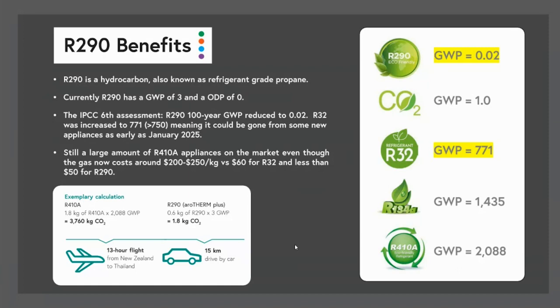So if we took an R410A appliance with 1.8 kilos of R410A, then you multiply that by its global warming factor, you get 3,760 kilos of CO2 as the environmental impact in terms of carbon footprint from that appliance if all of that refrigerant was released into the atmosphere. And that is equivalent to a 13-hour flight from New Zealand to Thailand, approximately.